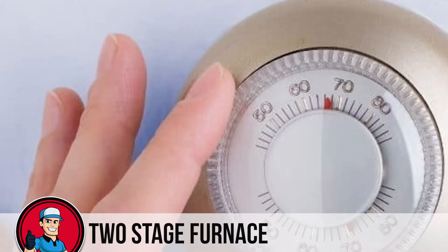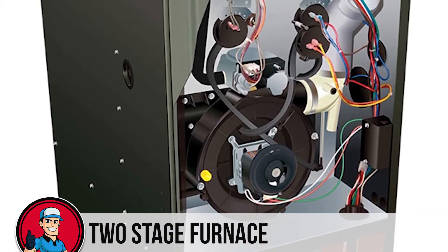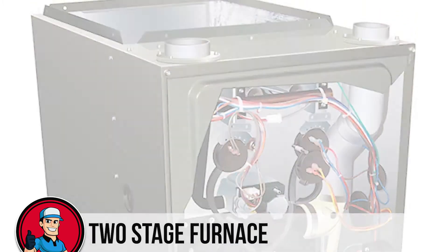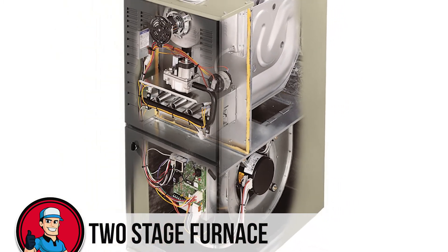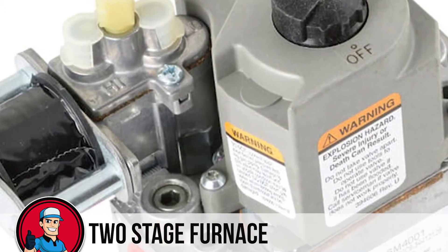Now let's talk about the two-stage furnace. A two-stage furnace has two modes when operational — a low and a high mode. The gas valve has two stages of operation: it is around 70% open at the low mode and fully open on the high. The furnace will automatically switch to the high mode if the temperature is very low and back to low when it is not that cold. That, coupled with the variable speed blower, can save costs, particularly if your heating costs are off the charts.